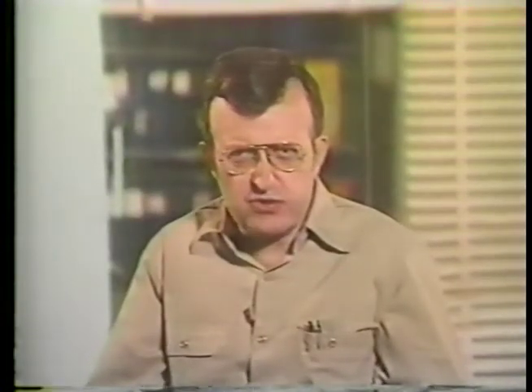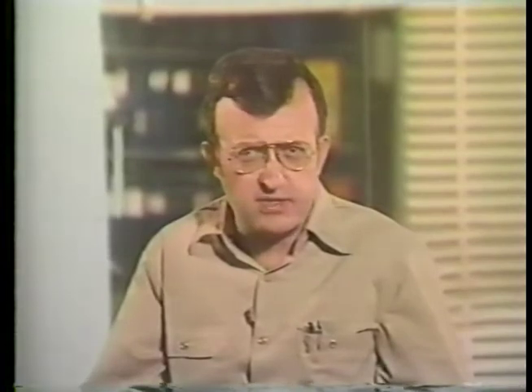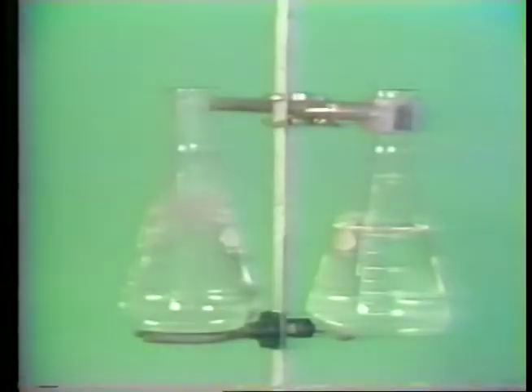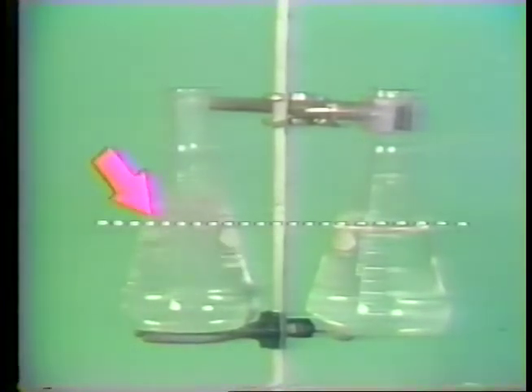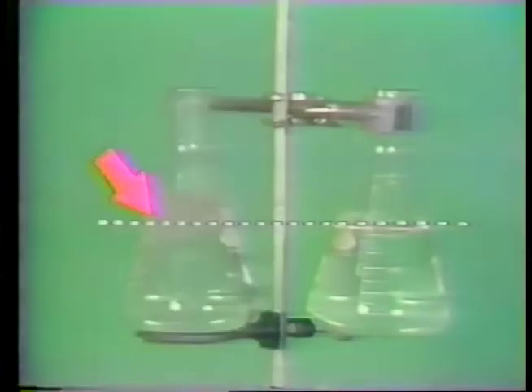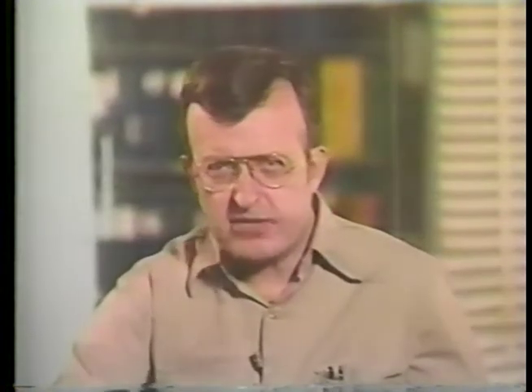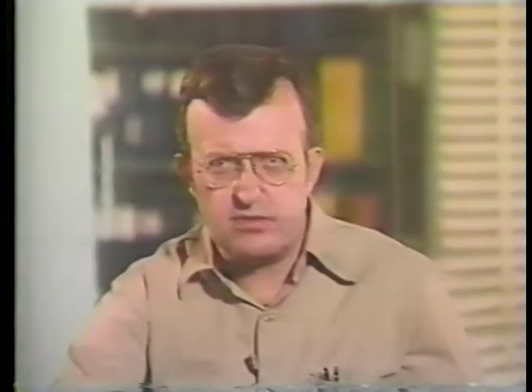From earlier training, you should know that as the temperature of water is increased, bubbles begin to form that increase the volume of a given quantity of water. For example, in this laboratory setup, the water level in this flask where boiling is taking place is higher than in this flask where no boiling is taking place. The increase in level is called swell. On natural circulation boilers, the increase due to swell may cause the level in the steam drum to exceed acceptable level specifications. This could cause water to overflow into the superheaters. By filling the drum to a level that is lower than normal operating level, you allow for the increase due to swell.